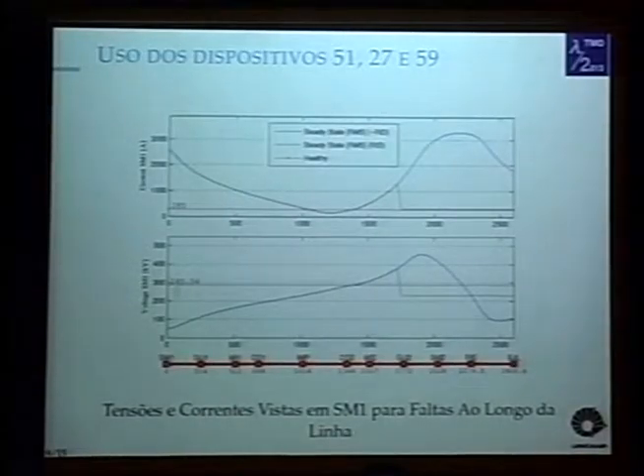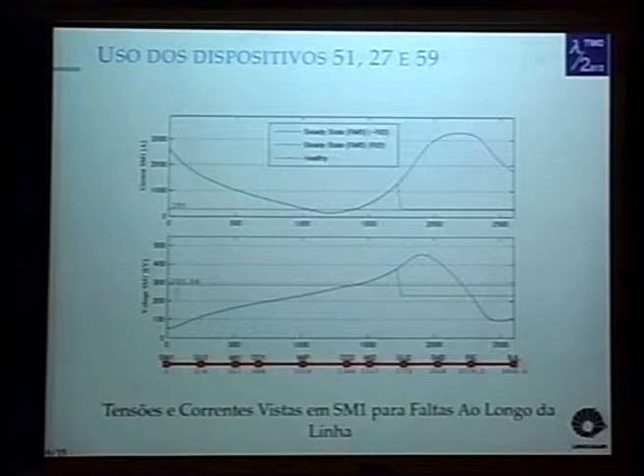After that, it begins to rise again, and after the final segment to larger currents, up to faults that happen in the Serra da Mesa 1 substation. In green, you can see that the reduced insulation distance had held these currents. So with that, we can see that it is possible to use overvoltage devices to cover the beginning and the end of the line. At least in this segment, if we use the reduced insulation distance, we can accomplish something. And for undervoltages at the beginning of the line and also at the end, and overvoltages as well. So in addition to the reduced insulation distance, we can also use this device.